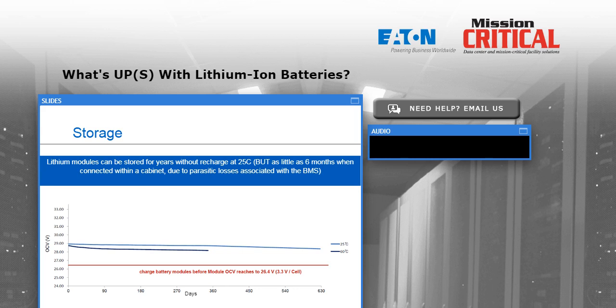That's encouraging, but keep in mind two important things. Most lithium batteries for UPS use will have a battery management system that does a little self-discharge over time, which can discharge the battery fairly rapidly, closer to 6 months. The batteries can be disconnected within the cabinet so that doesn't happen. But if the battery is connected in a cabinet and in storage, you should expect more like 6 to 9 months of storage life rather than 12 months.